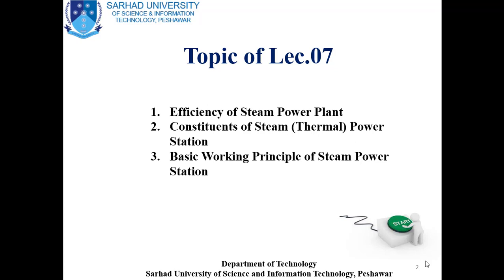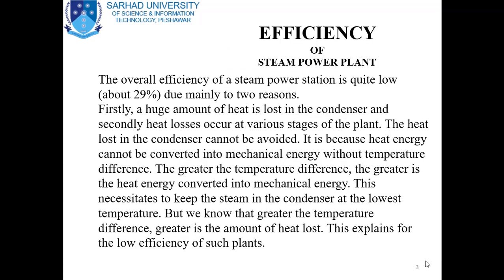Today we will cover these three topics. First is the efficiency of steam power plant. The overall efficiency of a steam power station is quite low — about 29% — due mainly to the following two reasons. Firstly, a huge amount of heat is lost in the condenser. Secondly, heat losses occur at various stages of the plant. The overall efficiency is approximately 29% because of these two reasons.